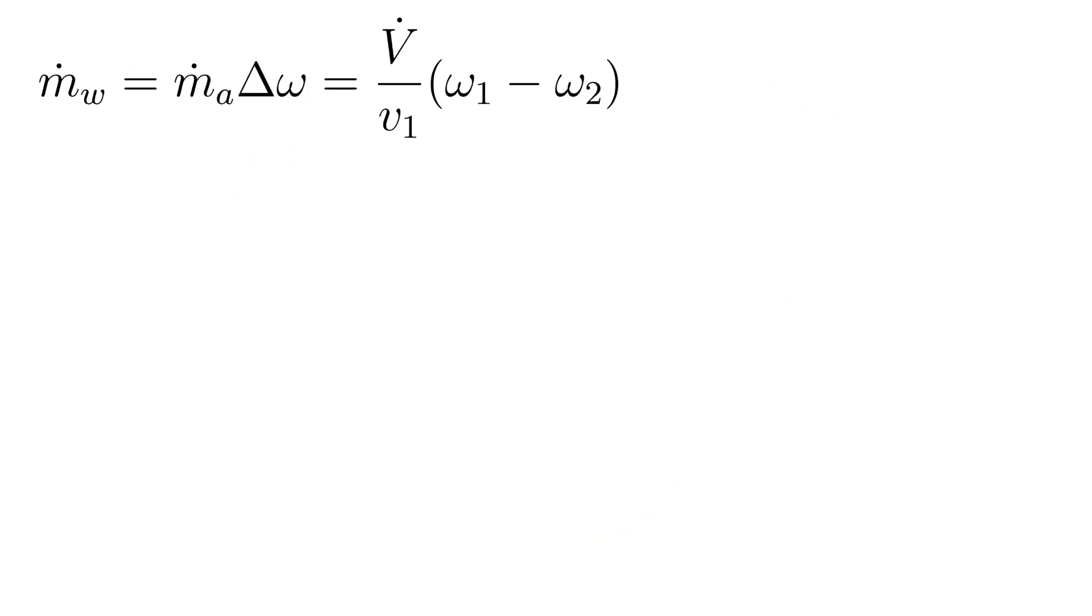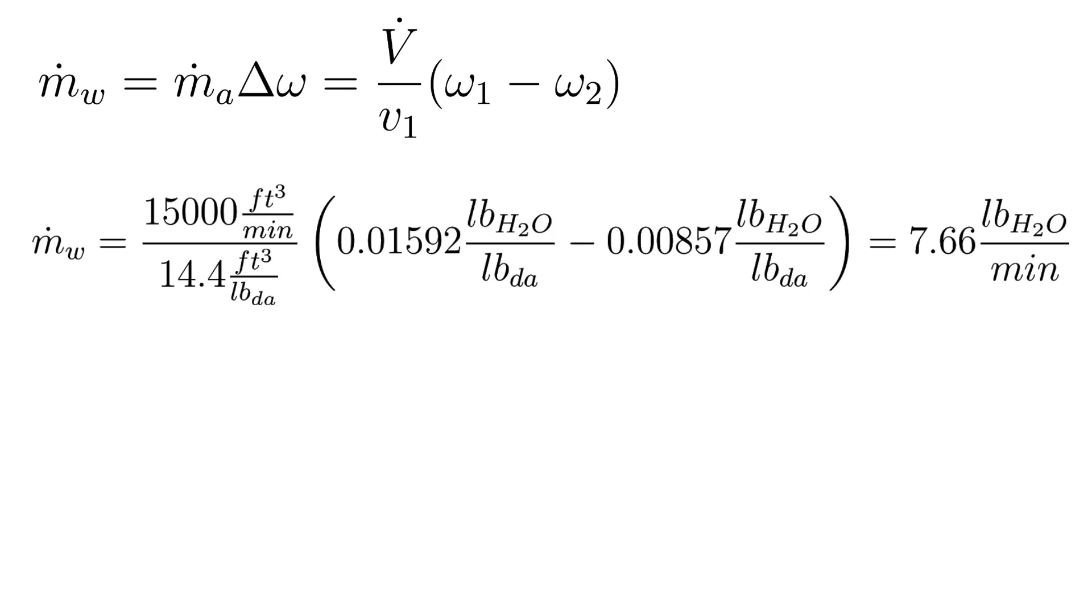Here's our equation again for finding the mass flow rate of condensate. Now let's plug in the volume flow rate, 15,000 CFM, the specific volume, 14.4 cubic feet per pound of dry air. The humidity ratio for each state as shown, and we can cross out the units, we'll be left with pounds of water per minute, and the answer is 7.66.